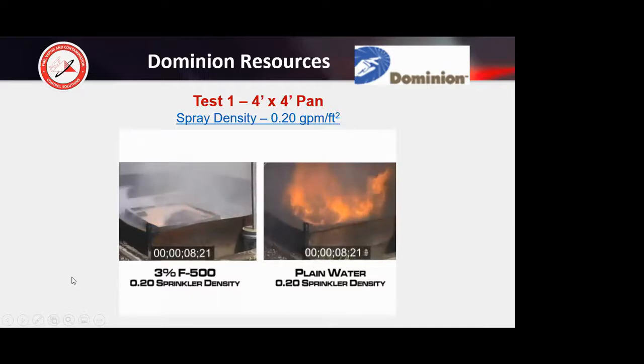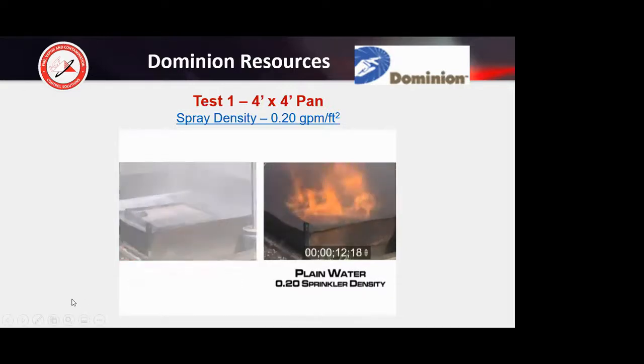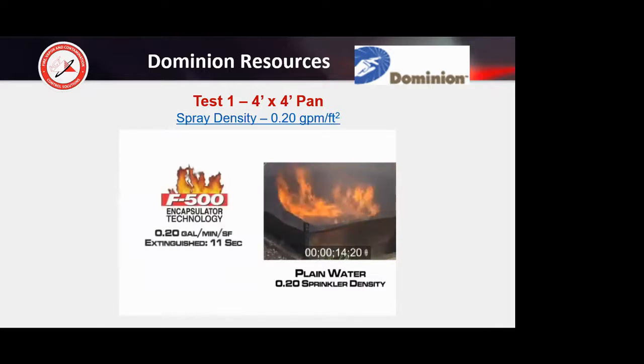So one of the things I want to note is we got a very quick knockdown here with the encapsulator agent. That's because we're encapsulating the vapor molecules. Second, with the rapid heat reduction, we're reducing the heat in this steel below the auto ignition temperature of the fuel. So with the F500 EA, we put the fire out in 11 seconds.